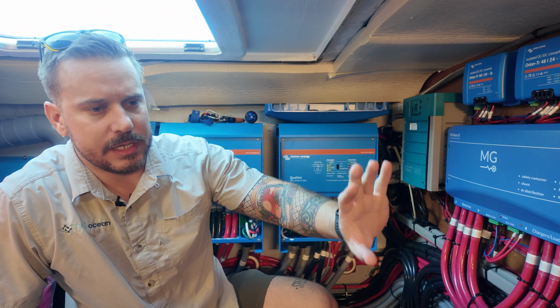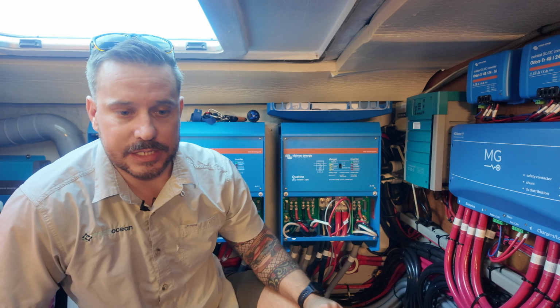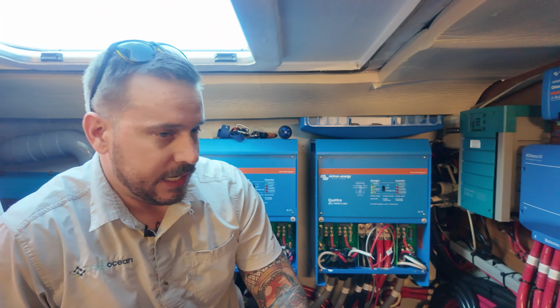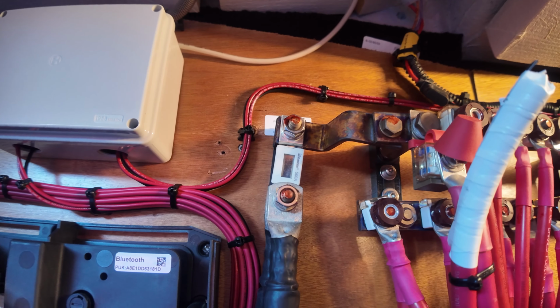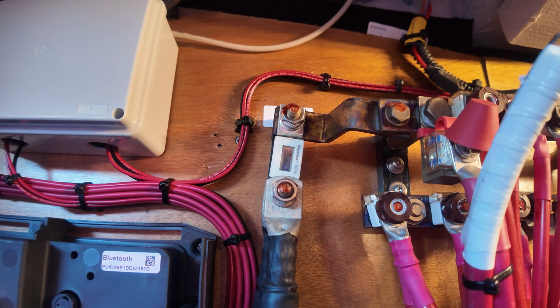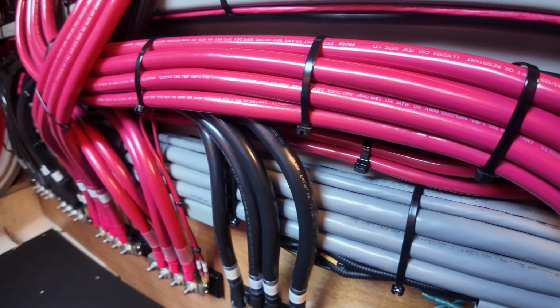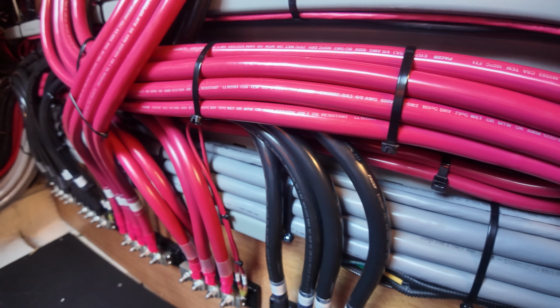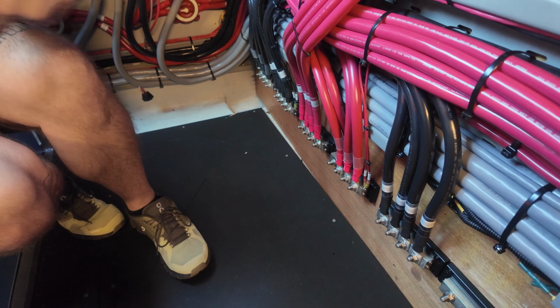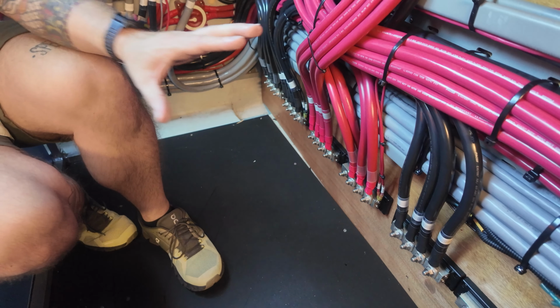So in order to do all this, it takes a bit of rearranging of existing wiring. As you can see, we've got the existing positive and negative bus bars over here, and what we've essentially done is created our own bus bar system down here for our batteries to interface with our battery management system. This gives you a pretty good idea of what it takes to actually install one of these systems to refit on a vessel of this size.